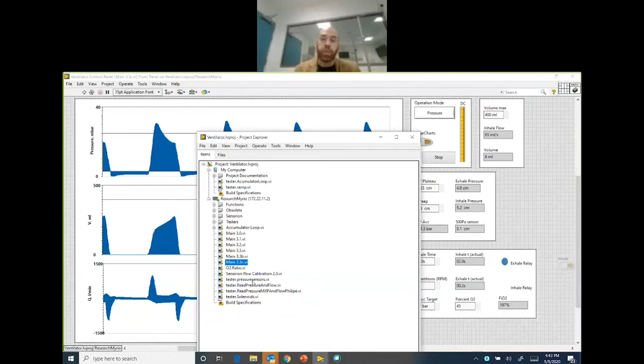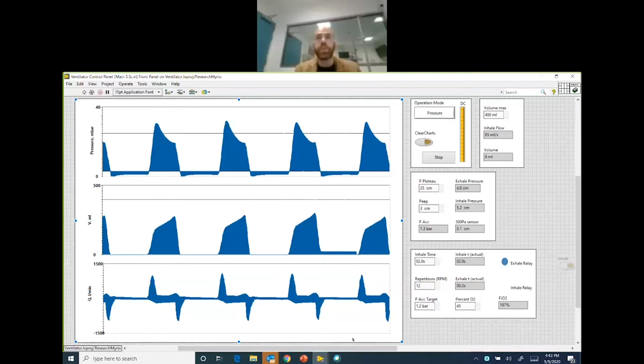We were very, very keen on making sure all those things are taken into consideration. Every single 3D part that is connected to the airways is going to be coated to make sure that we don't have degradation over time. All the industrial parts are biocompatible, and that's very important because we went through multiple iterations. We were using PVC, then we changed that because even though it is safe at pressures that low, we said no, we would go with something much more robust.